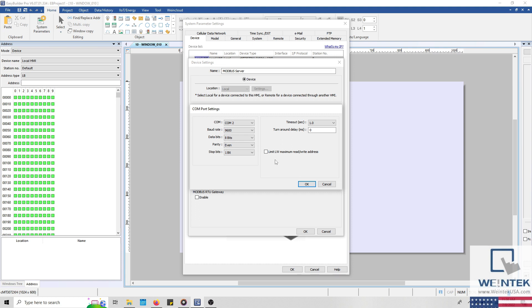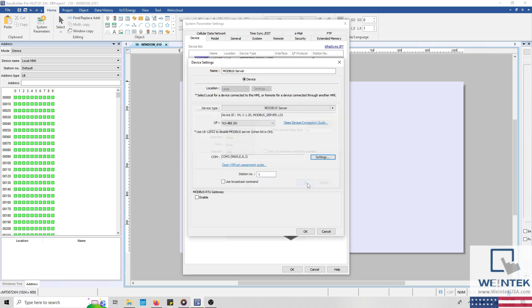And you'll notice a few additional options as well. For example, we can use the Limit LW maximum read slash write address to limit the LW addresses that are accessible to the master. It's important to note that LW addresses actually correspond to Modbus memory, but we'll discuss this more in a few minutes. And the turnaround delay can be used to delay the time in which the HMI responds to the next command. Below the communication parameters, we can define the Modbus station number. And at the bottom, we can enable our Modbus gateway.